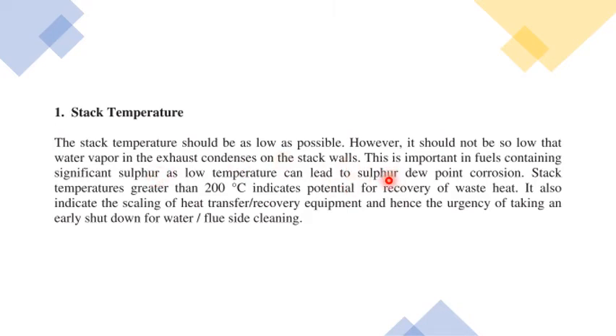From an energy consumption standpoint, if the flue gas temperature is greater than 200°C and you are not recovering that waste heat, it represents a significant energy loss. So you must keep the stack temperature low to minimize waste heat, but not too low — to avoid water vapor condensation and sulfur corrosion. Maintaining the stack temperature properly is the first energy conservation area for boilers.